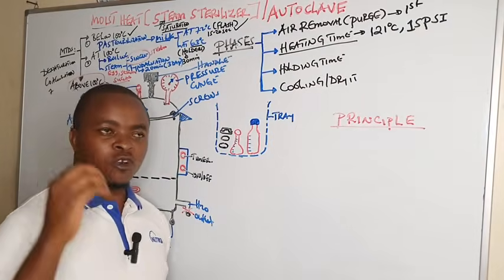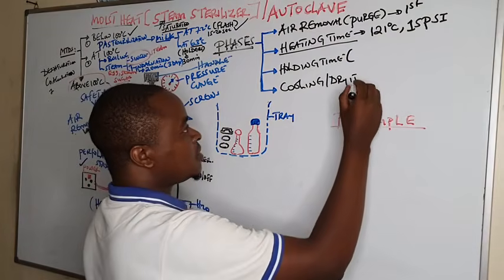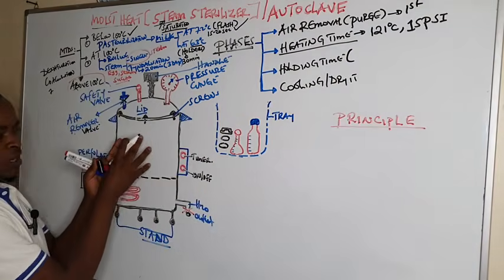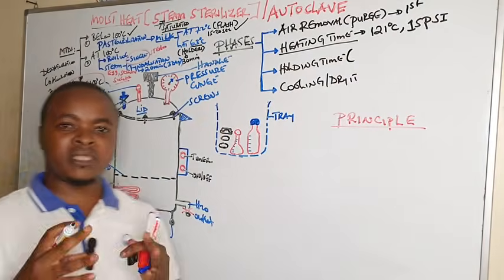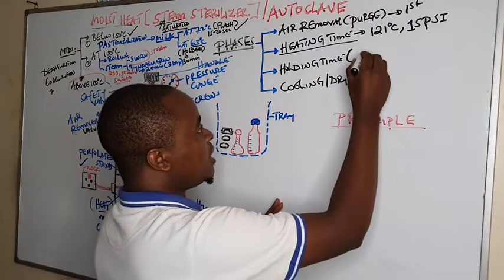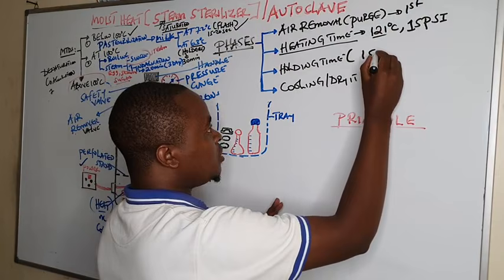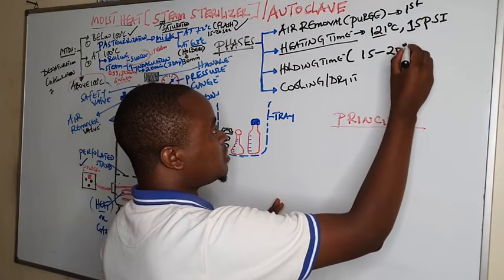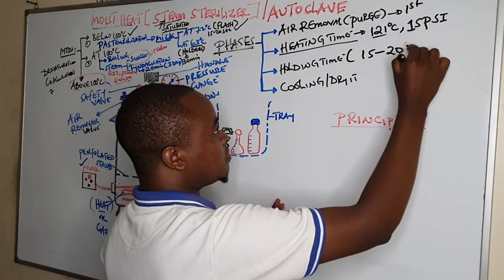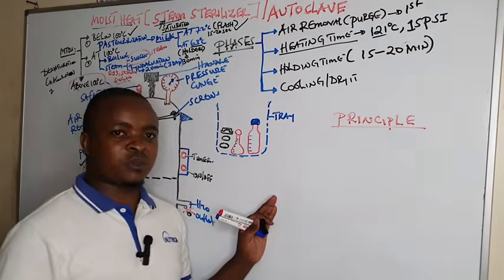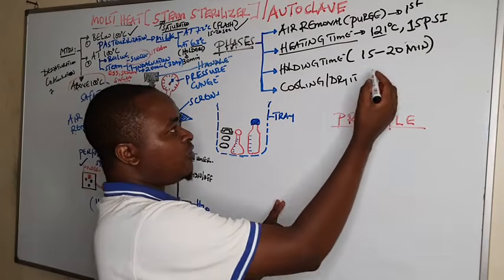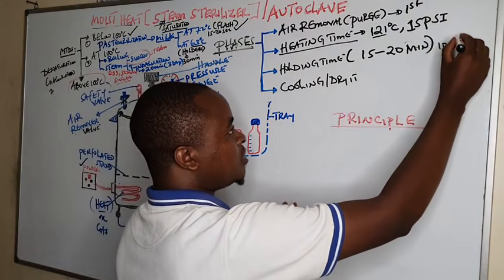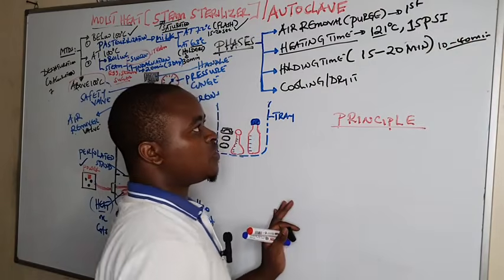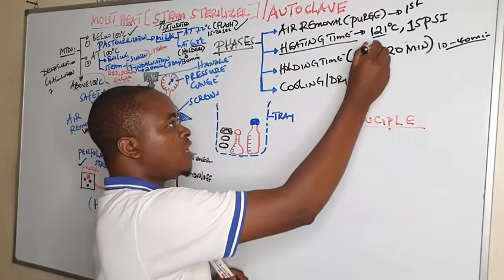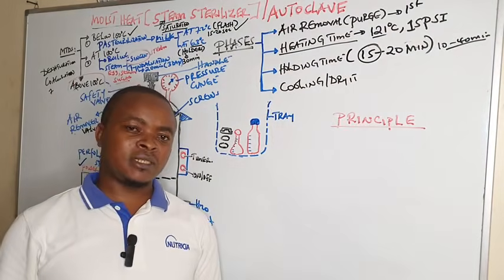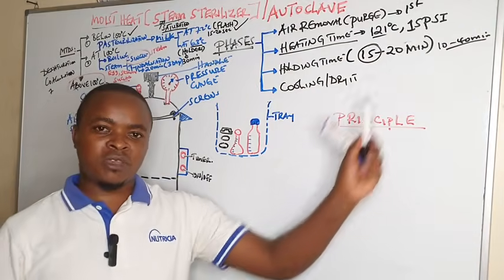Whereas holding time is the time it takes for the materials loaded in the autoclave to be sterilized. That is what we call holding time. Many times at 121 degrees, we use an average of 15 to 20 minutes, depending on the materials being autoclaved. This is the average, but sometimes it can range from 10 to 40 minutes, depending on the materials being autoclaved. But the most commonly used in the hospital setting is 15 minutes as the holding time.